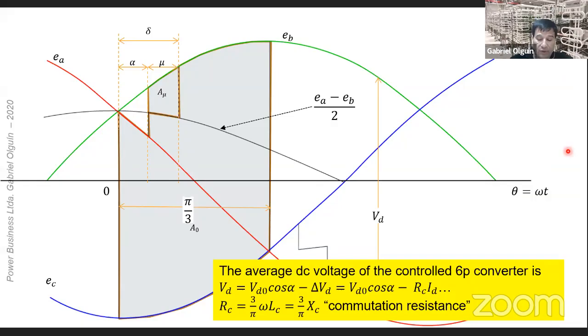This figure shows a detail of the commutation process between valve 1 in phase A and valve 3 in phase B. Because of the commutating phenomena, the converter terminal voltage does not reach the incoming voltage EB. So this voltage should rise up to EB, but that doesn't happen because of the commutating phenomena. So there will be a reduction in the average voltage due to this phenomena, and that can be modeled using this equation.